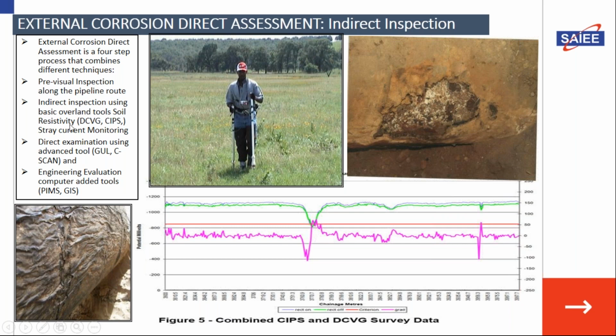These tools include soil resistivity using a four-pin method, and direct current voltage gradient method. With this method, when protecting your pipeline against corrosion, you inject electricity into the pipeline. Given that the pipe has a coating, a voltage gradient builds up wherever there's a coating defect. You pick that up by walking along the pipeline with probes, having copper sulfate half cells at the end, and a high resistance analog voltmeter - the needle increases at the voltage gradient and you can identify the coating defects.